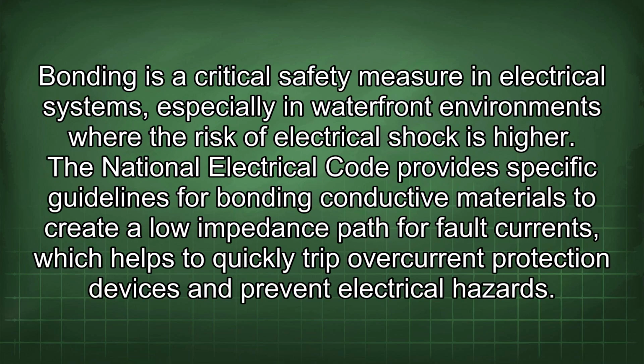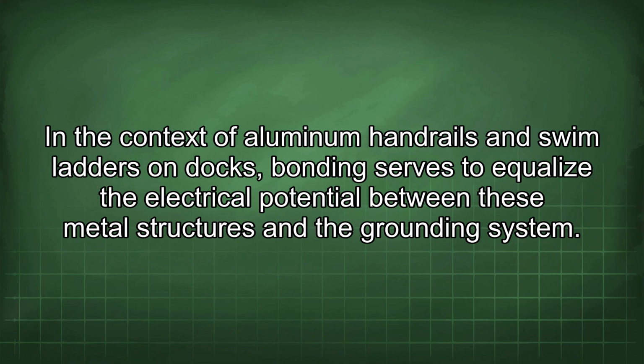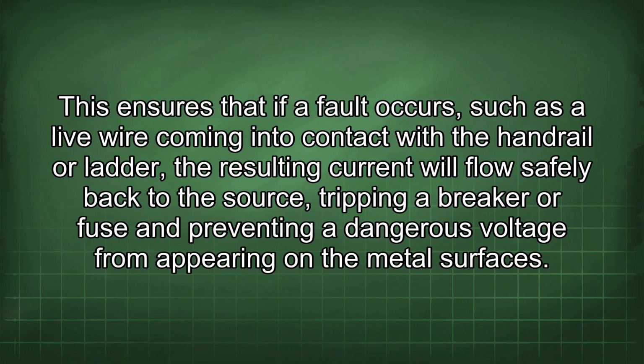Bonding is a critical safety measure in electrical systems, especially in waterfront environments where the risk of electrical shock is higher. The National Electrical Code provides specific guidelines for bonding conductive materials to create a low impedance path for fault currents, which helps to quickly trip overcurrent protection devices and prevent electrical hazards. In the context of aluminum handrails and swim ladders on docks, bonding serves to equalize the electrical potential between these metal structures and the grounding system. This ensures that if a fault occurs, such as a live wire coming into contact with the handrail or ladder, the resultant current will flow safely back to the source, tripping a breaker or fuse and preventing a dangerous voltage from appearing on the metal surfaces.